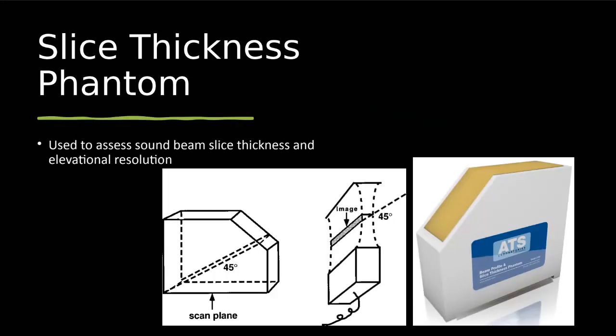Next is our slice thickness phantom. So this is used to assess the sound beam slice thickness and elevational resolution. I haven't seen this one used too often. I'm used to seeing physicists bring in that tissue equivalent phantom and also the Doppler phantom, but I haven't really seen this being used clinically, so I'm not too familiar with how they actually evaluate the slice thickness on these phantoms.